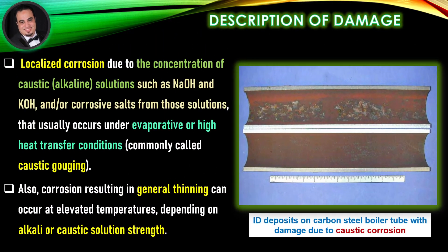Description of damage: Localized corrosion due to the concentration of caustic, alkaline solutions such as sodium hydroxide and potassium hydroxide, and/or corrosive salts from those solutions, that usually occurs under evaporative or high heat transfer conditions. Commonly called caustic gouging. As illustrated in the figure, inside diameter deposits on carbon steel boiler tube show damage due to caustic corrosion.